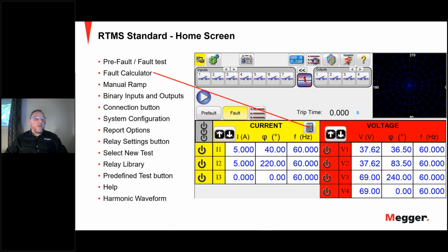The fault calculator is composed of the modes, fault type, healthy values, fault values, output waveform, and percentage of harmonics. This will reveal a selection list for the different types of test options like overcurrent mode, voltage mode, frequency mode, impedance mode, symmetrical mode, power swing mode, and fault location mode. So it is very easy to set up a typical fault in the fault calculator and run it off the home screen to see how the relay will perform.